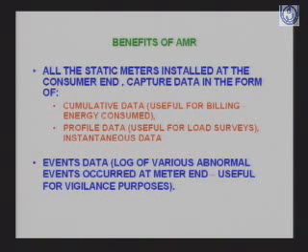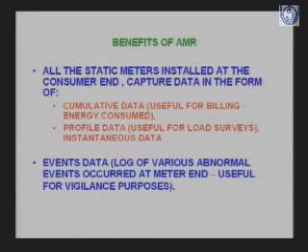Now, the benefits of AMR: all the static meters installed at the consumer end capture data in the form of cumulative data useful for billing, profile data useful for load surveys, instantaneous data, and events data, a log of the various abnormal events. Now in this process, when the vehicle is moving and taking readings, there may be certain problems, there may be certain interruptions, and the system generates a log of the problems encountered, and these problems are looked at by the vigilance section for business monitoring.